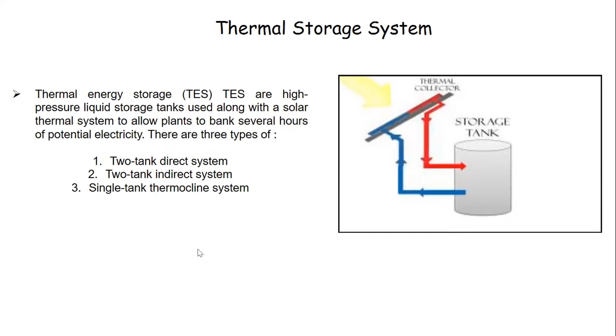In a two tank direct system, solar thermal energy is stored in the same fluid used to collect it. The fluid is stored in two tanks, one at high temperature and one at low temperature. Fluid from the low temperature tank flows through the solar collector or receiver, where solar energy heats it to a high temperature, and it then flows to the high temperature tank for storage. Fluid from the high temperature tank flows through a heat exchanger where it generates steam for electricity production. The fluid exits the heat exchanger at a low temperature and returns to the low temperature tank.